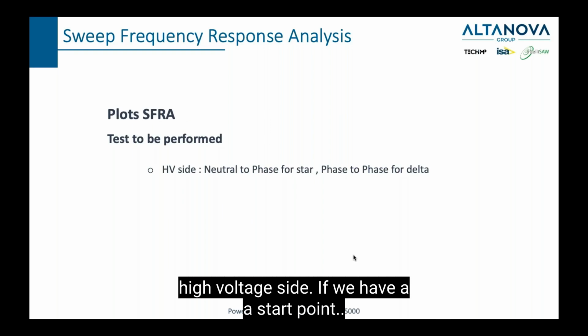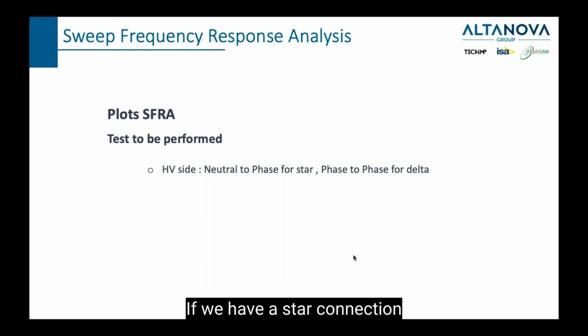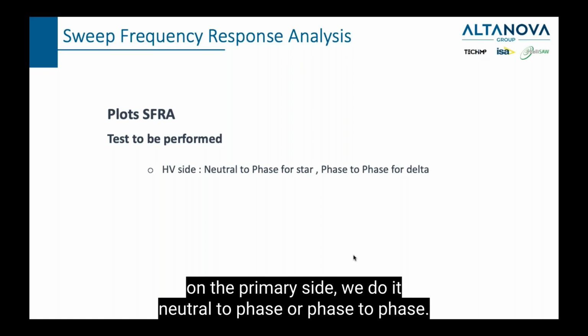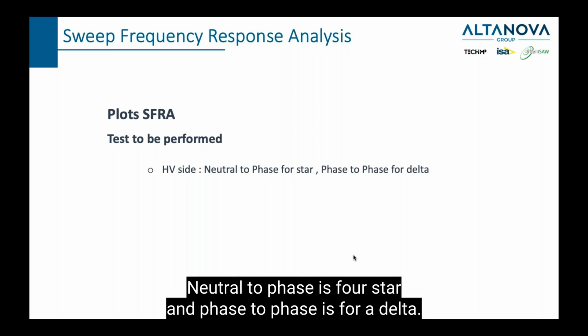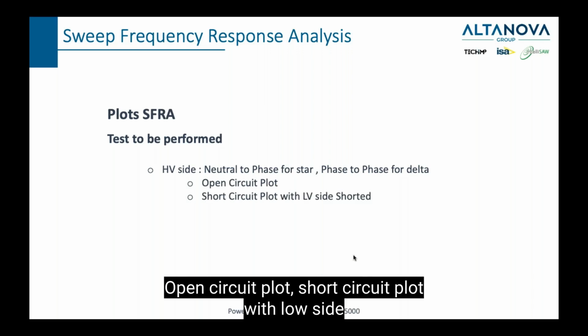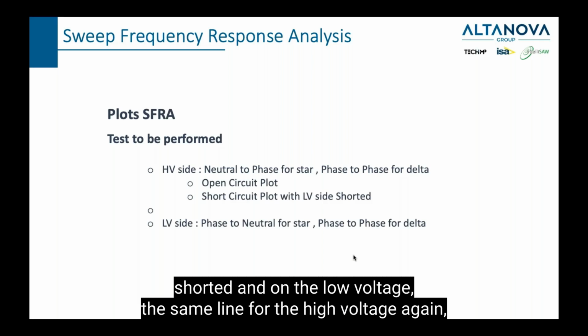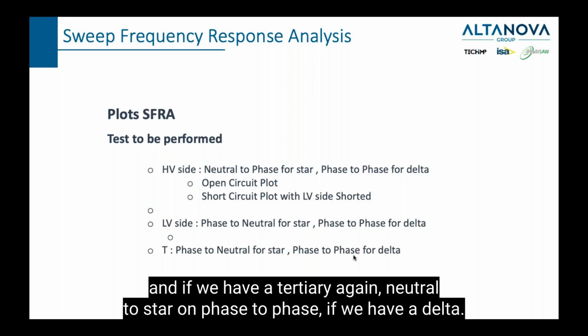If we have a star point, if we have a star connection on the primary side, we do it neutral to phase or phase to phase. Neutral to phase is for a star and phase to phase is for a delta. Open circuit plot, short circuit plot with LV side shorted, and on the low voltage, the same as for the high voltage again.